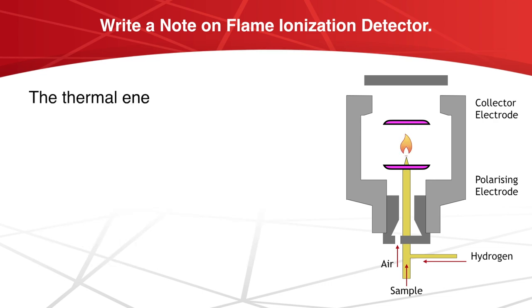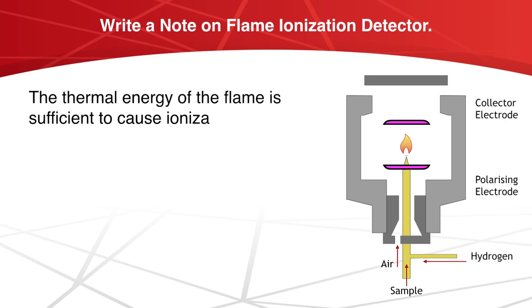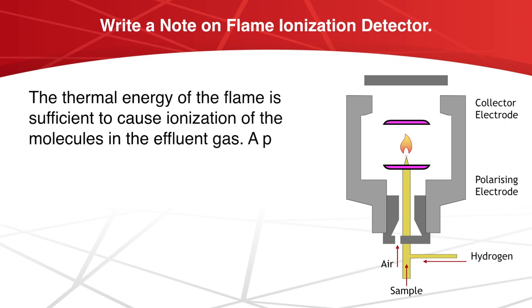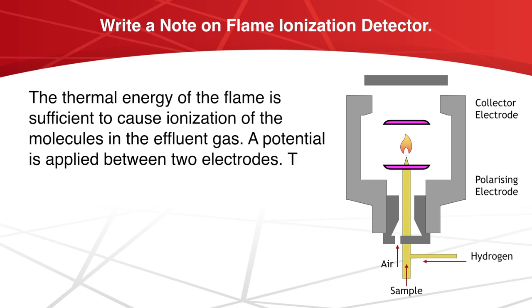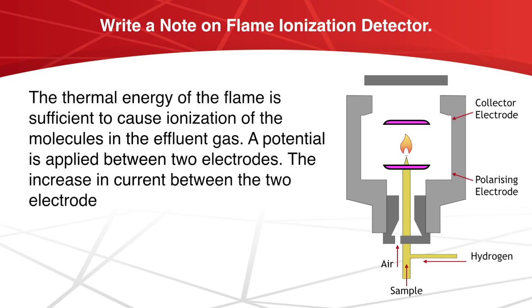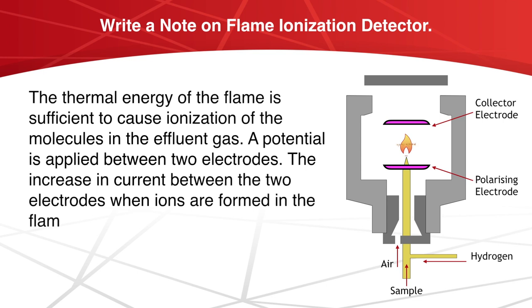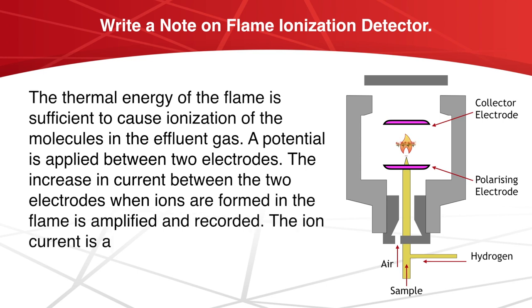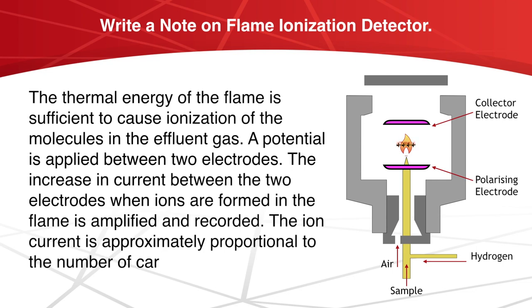The thermal energy of the flame is sufficient to cause ionization of the molecules in the effluent gas. A potential is applied between two electrodes, and the increase in current between the two electrodes when ions are formed in the flame is amplified and recorded. The ion current is approximately proportional to the number of carbon atoms which enter the flame.